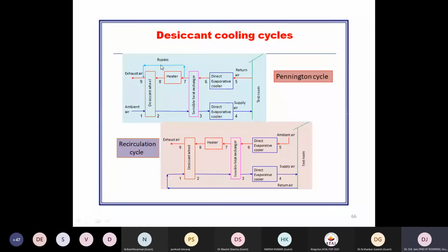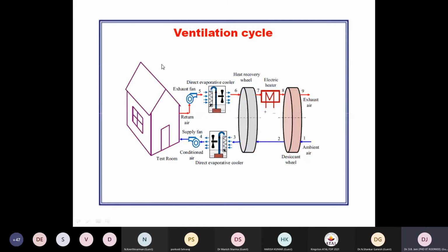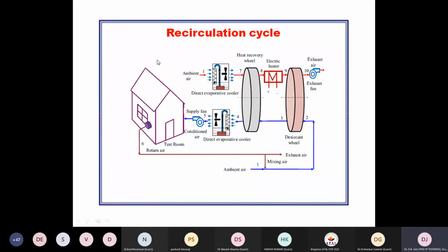Different desiccant cycles are distinguished by whether the return room air or fresh ambient air is used, called the ventilation cycle or recirculation cycle. Sometimes you may use a combination with a direct evaporative cooler for the cooling in the case of desiccant. Sometimes a recirculation mode will be used, where partially ambient air, say 5% or 10%, gets mixed with the recirculation air, and the same is circulated through the system.